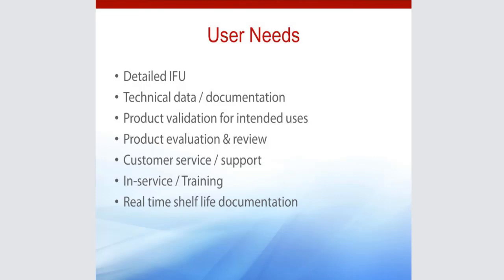I would also encourage you to have the customer service and support information, the phone numbers or the email for all the products, so that when you need them at a time when it's a little stressful, you don't have to go searching for them. So that's another good thing to keep along with the IFUs. When you change to new products, the reprocessing instructions are included on items in their IFUs. If they do not include reprocessing, meaning how to clean, disinfect, and/or sterilize, then that item is considered a single-use product and it cannot be reprocessed.